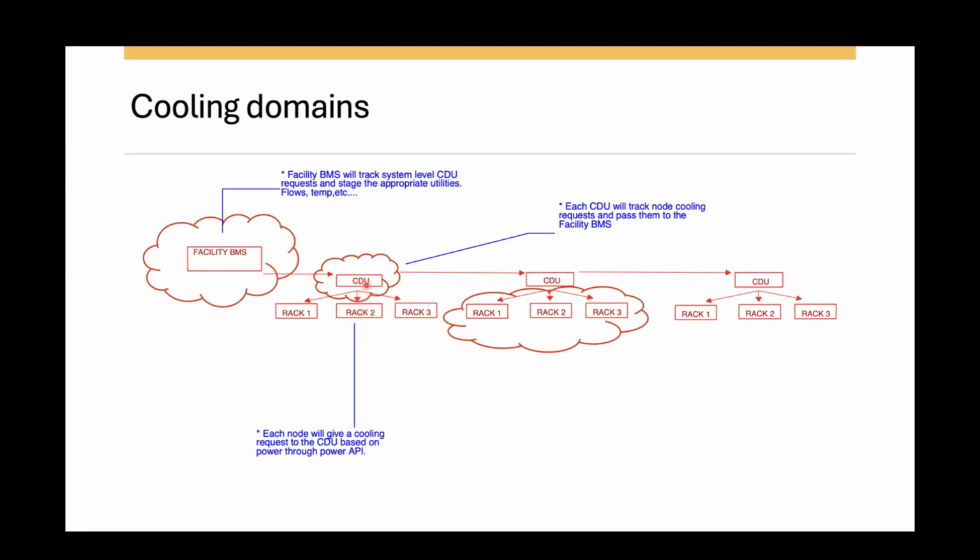The CDUs themselves can be using PowerAPI to then set conditions or report conditions back to a BMS. So what's happening here is the PowerAPI is useful not only for the user, it can also be used to write some of the software underneath, such that a rack can be ambivalent to the type of CDU that it is communicating with, because it can use PowerAPI as a whole.